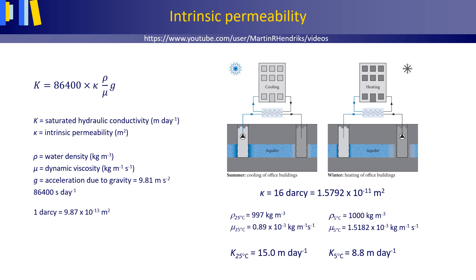Let's imagine that we have an aquifer with an intrinsic permeability kappa of 16 Darcy. In the Netherlands, almost all aquifer thermal energy storage projects operate at a relatively small temperature range between 5 and 25 degrees Celsius. Given the water densities Rho and dynamic viscosity Mu at injection temperatures of 5 and 25 degrees Celsius, we can estimate the saturated hydraulic conductivity at these temperatures.